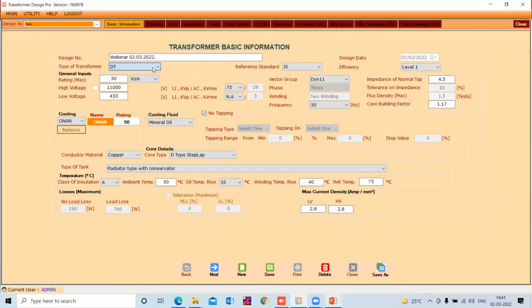Let's look at the rating of the transformer. What rating do you wish to go for? Let's decide and go for 1500 kVA. Okay, good enough. You can set the primary voltage. There is also a checkbox that indicates you can go for dual voltage for the HV winding. So 11,000 for the high voltage, and low voltage you have chosen to be 433. You can choose as much as you want.